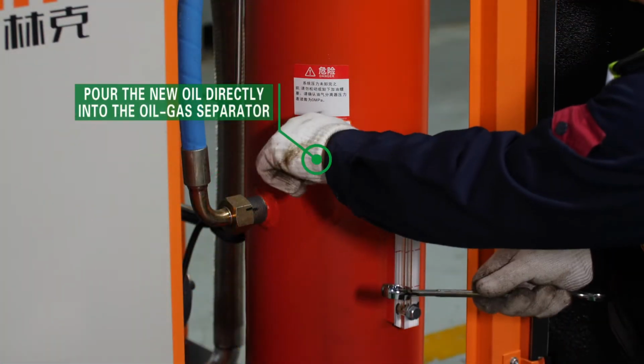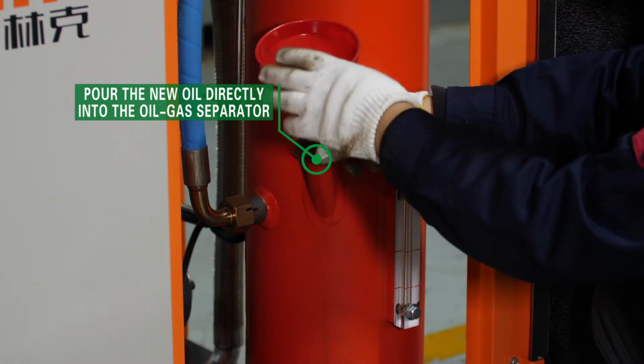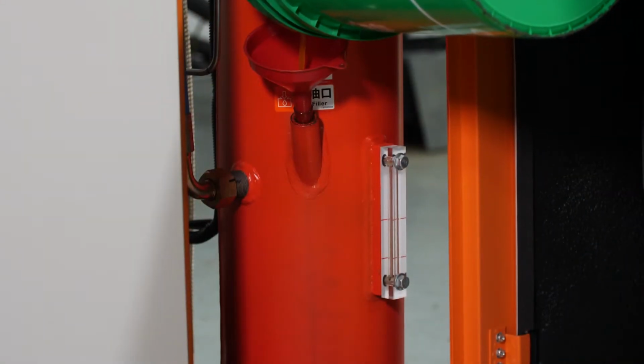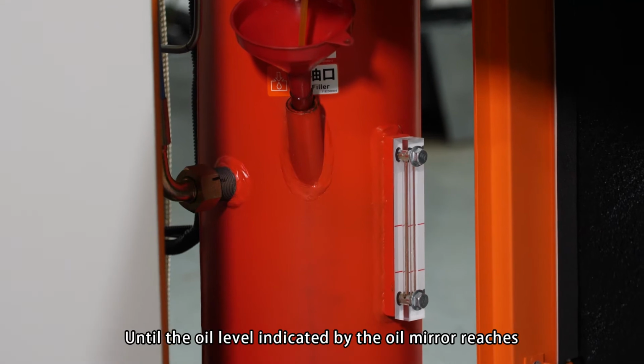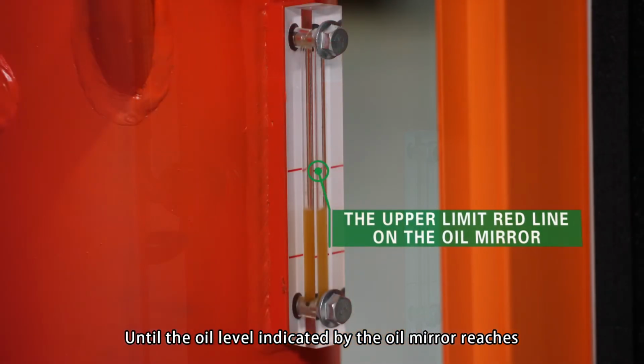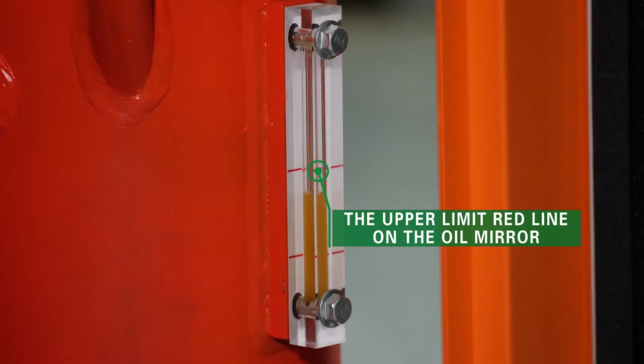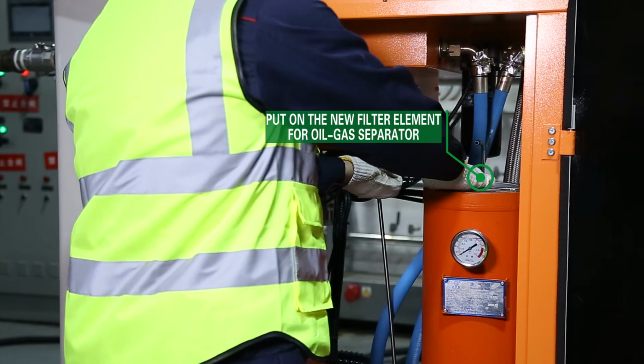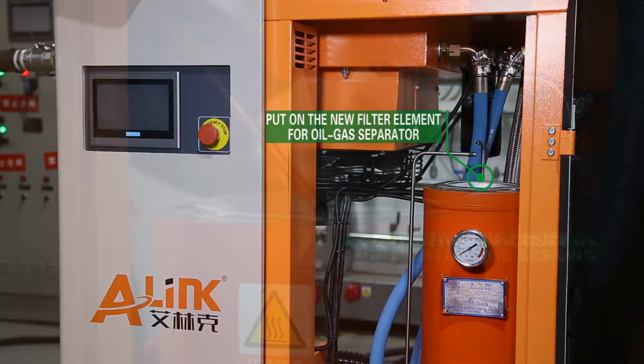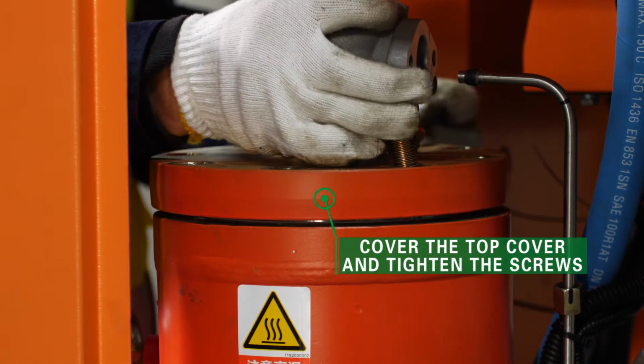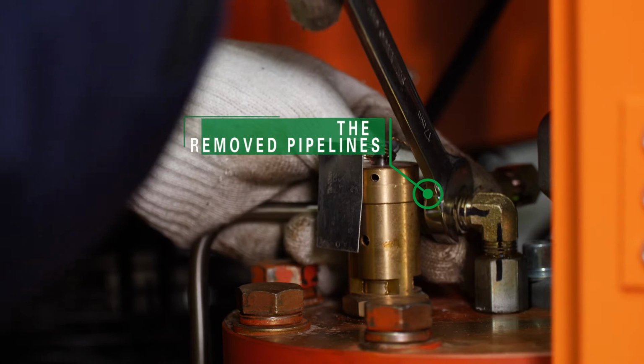Pour the new oil directly into the oil-gas separator until the oil level indicated by the oil mirror reaches the upper limit red line on the oil mirror. Put on the new filter element for oil-gas separator. Cover the top cover and tighten the screws. Finally, connect all the removed pipelines.